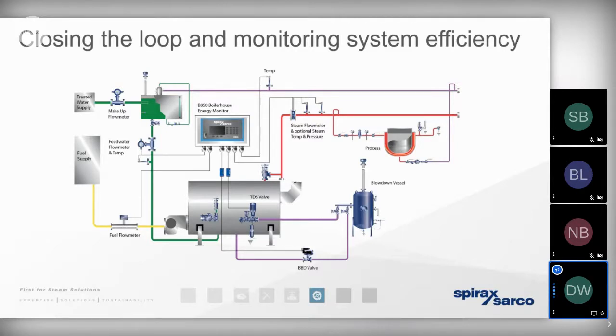And this really helps us to understand the mass and energy balance between taking a reading from the water coming into the building, the fuel coming to the boiler, the feed water leaving the hot well, and the steam that's leaving the boiler. Because by taking a mass and energy balance of all of these readings, it can determine when we're at a point when condensate is going missing. And when that is brought to our attention, we can walk the plant and we can identify why that is. Typically, it's going to be down to failed steam traps, down to an excess of flash steam that's vented away, or down to condensate pumps that aren't operating efficiently.